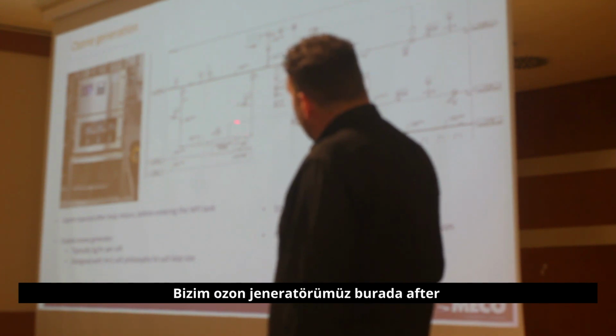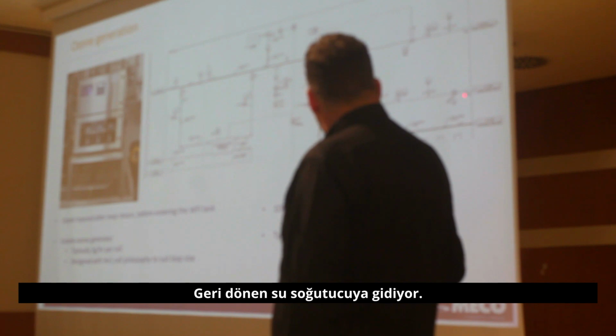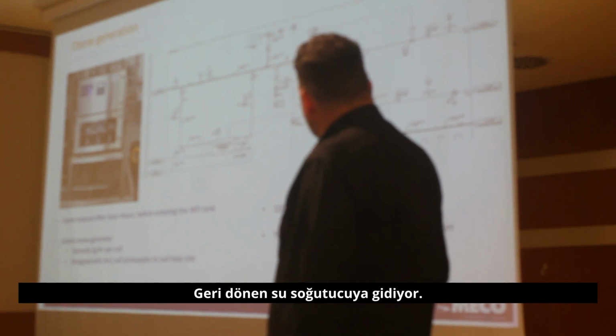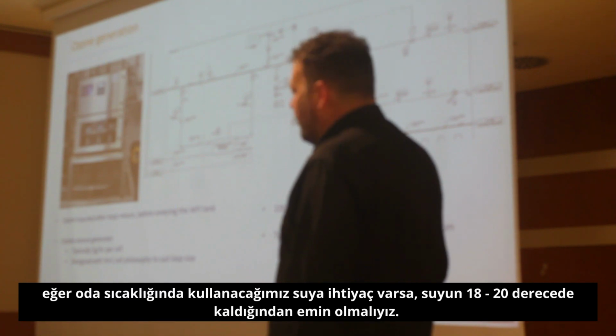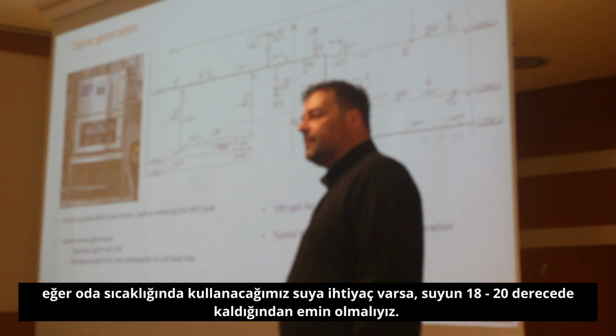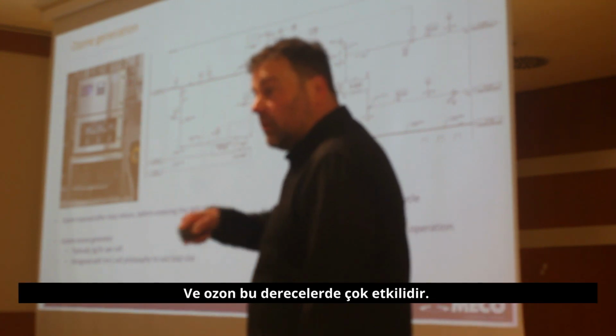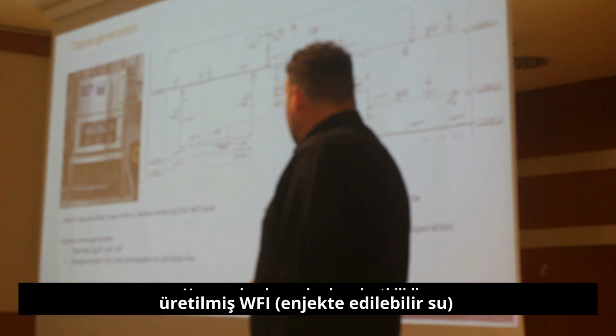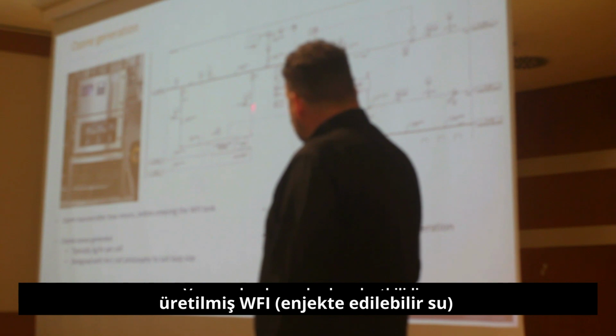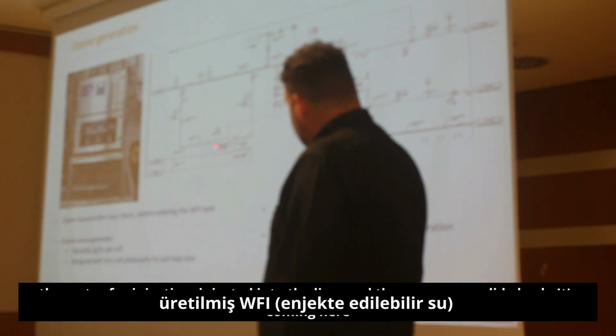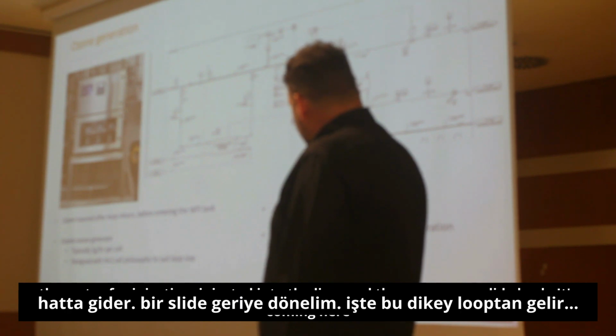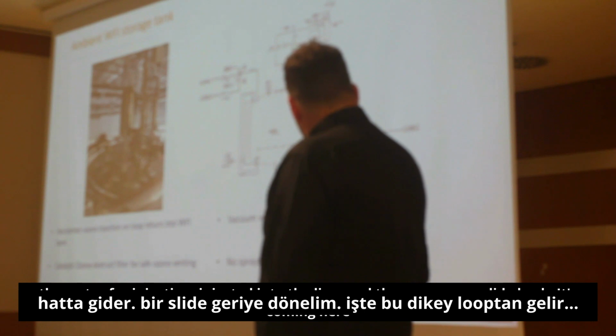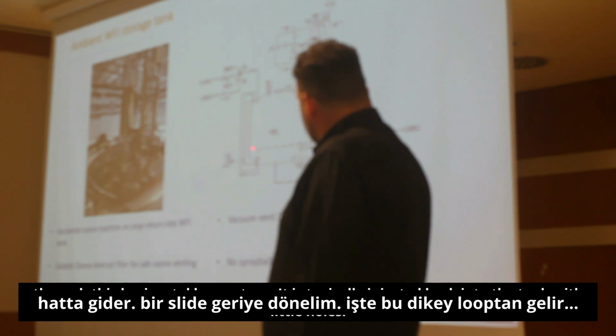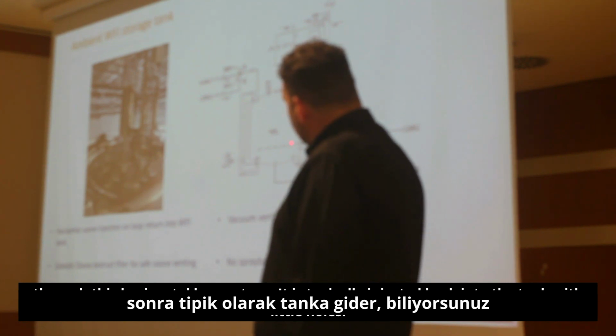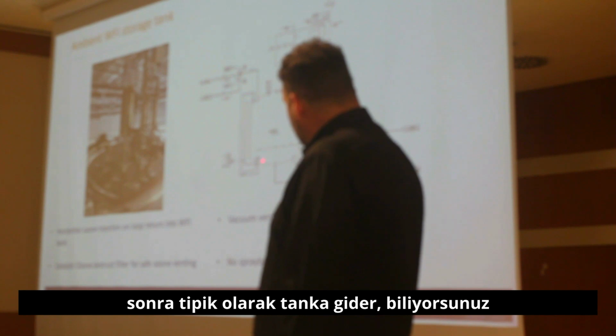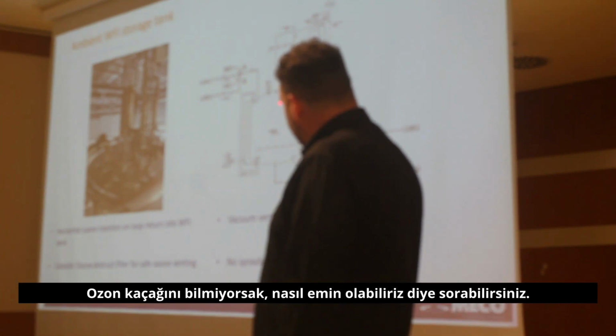So on the P&ID, we have our ozone generator here. This is your line coming back from your loop, from your points of use. We're going to a cooler because when we have an ambient system, we need to make sure the water remains between 18 to 20 degrees. And that is also when ozone is at its best, at these temperatures. So ozone is generated from the water for injection, injected into the line, and then we go one slide back. It's coming here through this vertical loop return. It is typically injected back into the tank with little holes. So the ozonized water is going to bubble up and fill the tank.